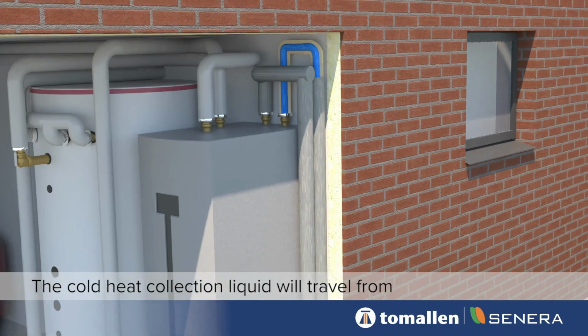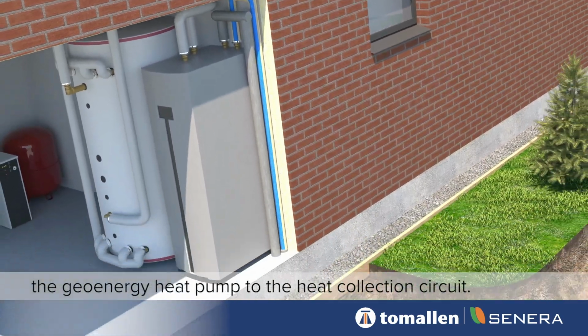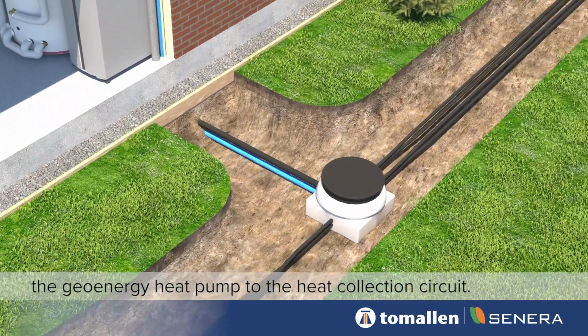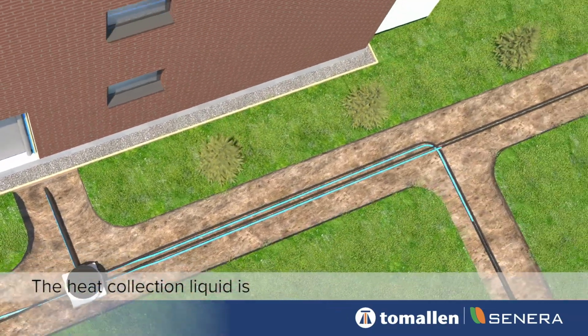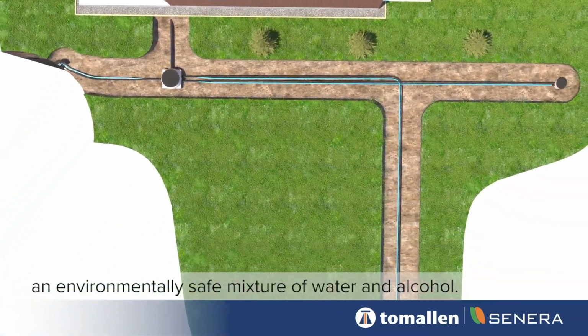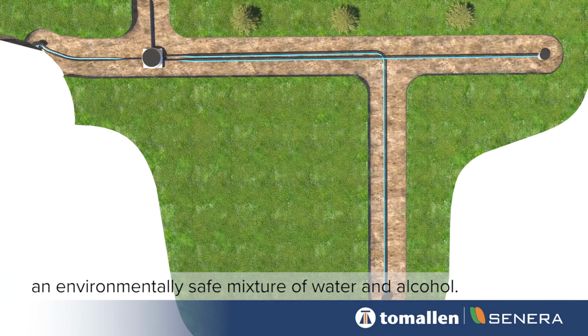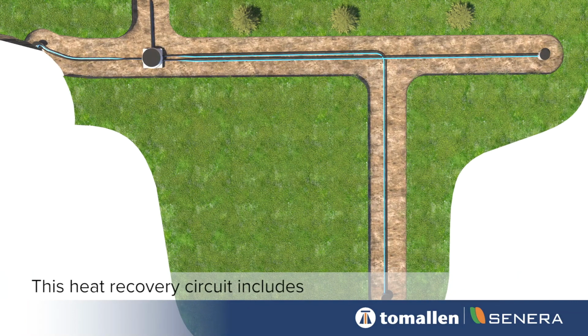The cold heat collection liquid will travel from the geoenergy heat pump to the heat collection circuit. The heat collection liquid is an environmentally safe mixture of water and alcohol. This heat recovery circuit includes a collection well and 3 energy wells. The energy wells are spread as far apart on the plot as possible. Their depth and number will be determined based on the heat energy needed.